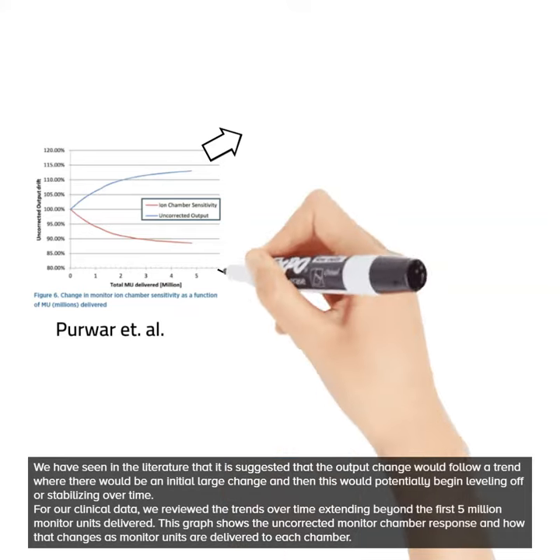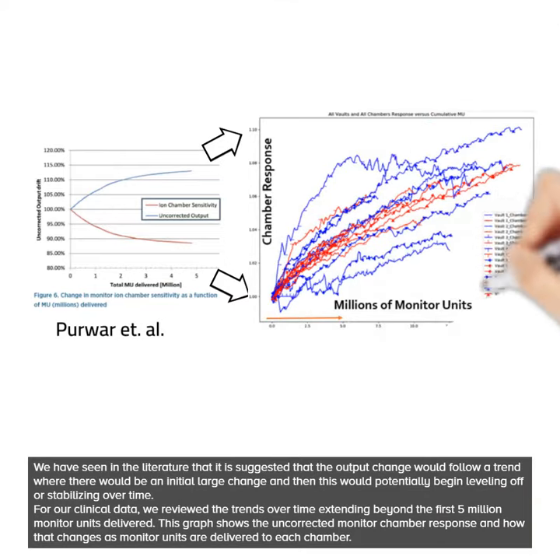For our clinical data, we reviewed the trends over time extending beyond the first 5 million monitor units delivered. This graph shows the uncorrected monitor chamber response and how that changes as monitor units are delivered to each chamber.